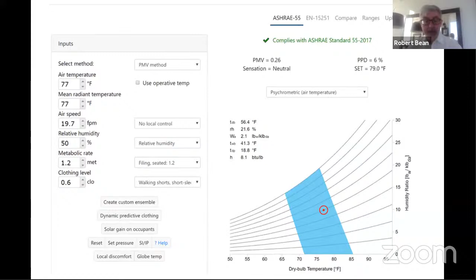And then as we change that, we can look at how it affects the compliance. This slide shows the PPD, which is 6%. It's in compliance with ASHRAE Standard 55 based on these input values. There's this graphical area, the shaded area, that represents the comfort zone, and that dot represents the person in the space. So here we have a combination of air temperature, mean radiant temperature, airspeed, relative humidity, MET rate, and clothing, where we are in fact compliant with the space.